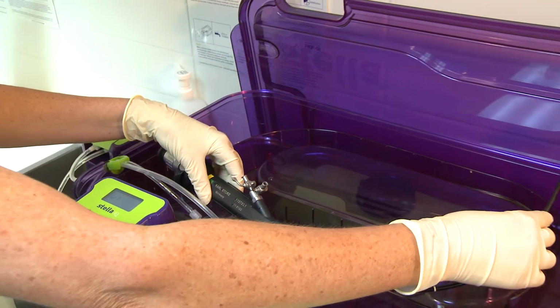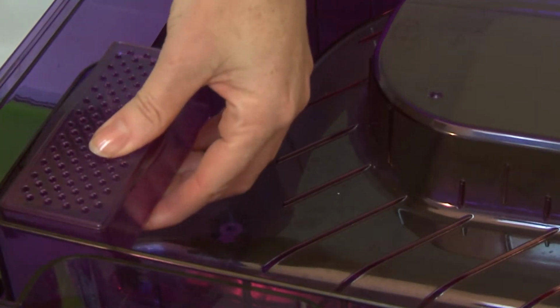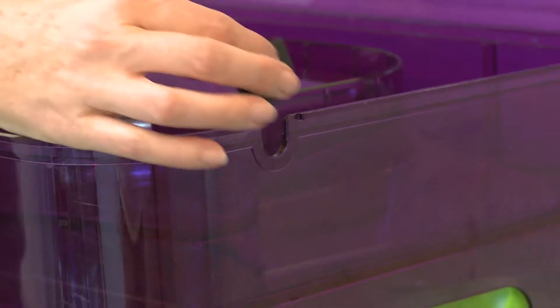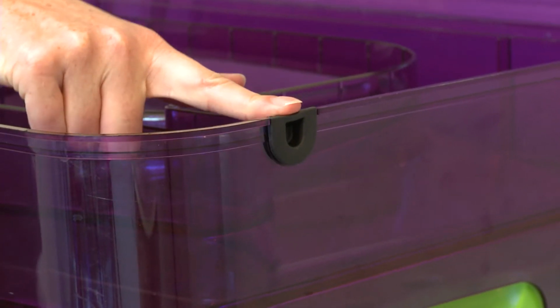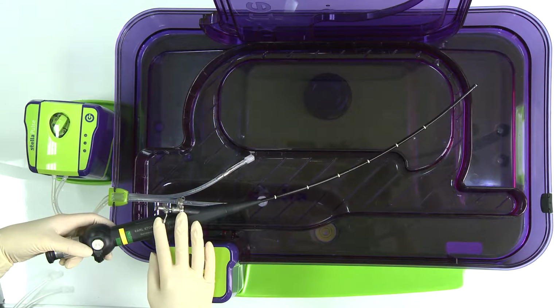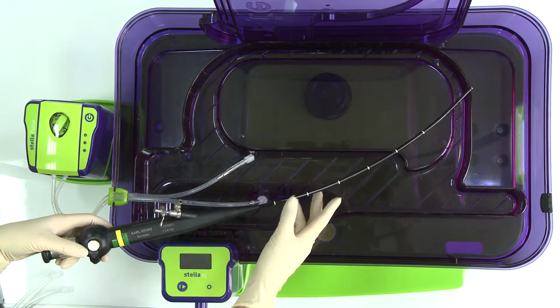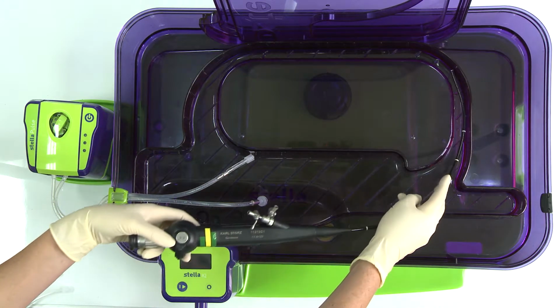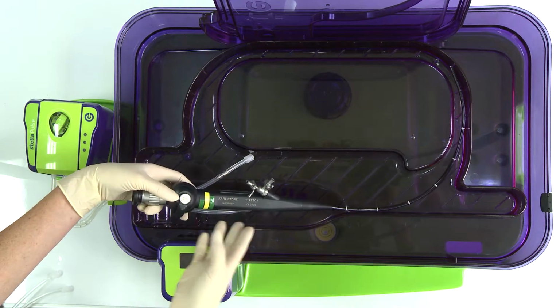Place the pre-cleaned instrument into the inner instrument compartment of the base and lock the small parts tray into place. Seal the grommets where instrument parts are not exiting from the base. This instrument is a Storz cystoscope which has a working lumen. Connect the tube set luer lock connector to the instrument lumen port.